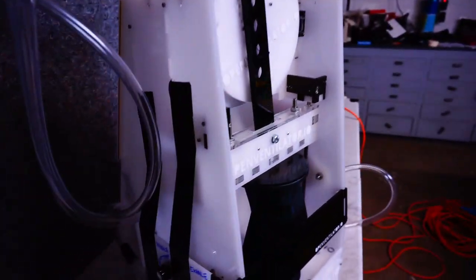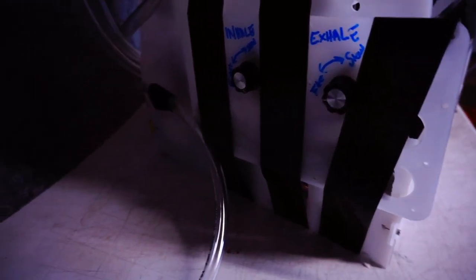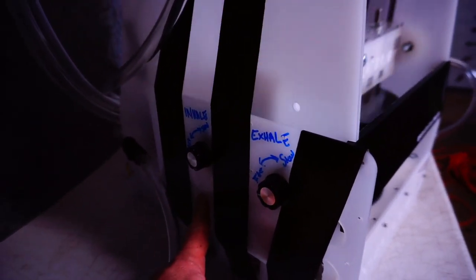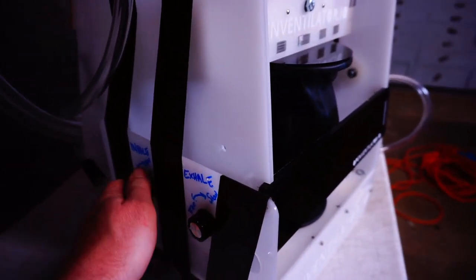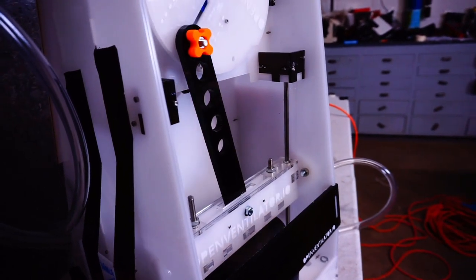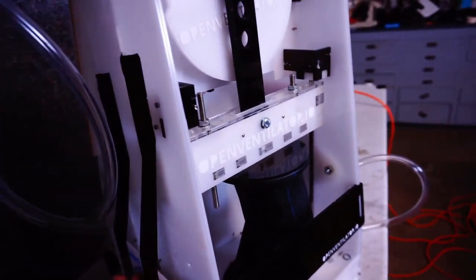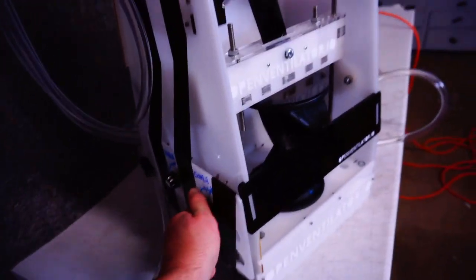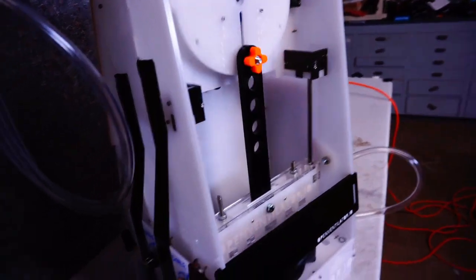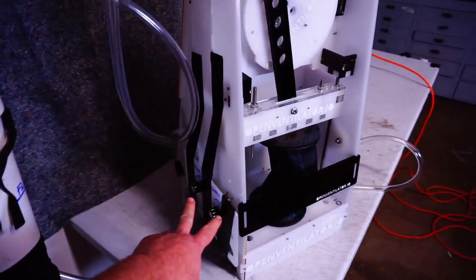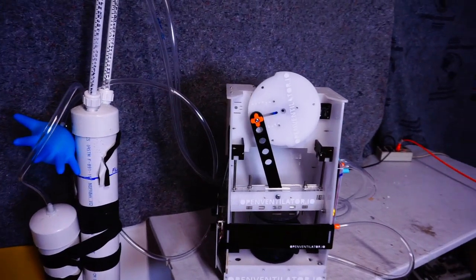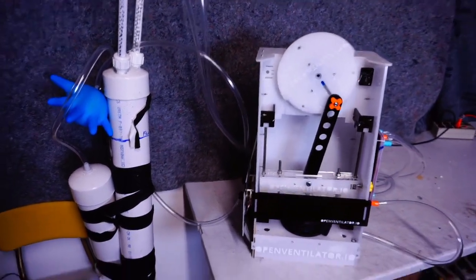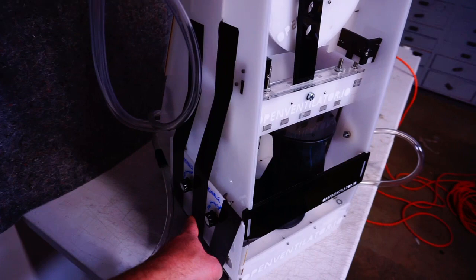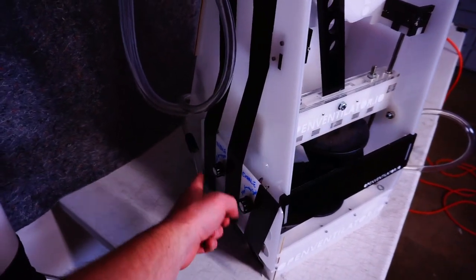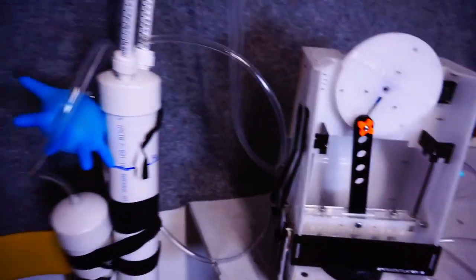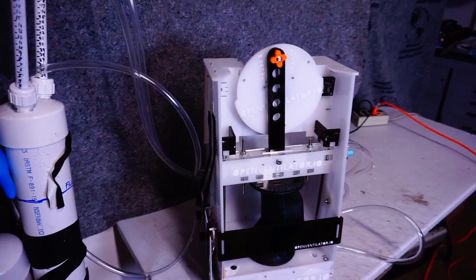Okay, so over here, pardon my electronics mounting, we have an exhale speed and an inhale speed. We're now, let's say, on the inhale cycle. We can slow that way down, or speed it way up, and the same for the exhale. By changing these two speeds, we can change the ratio of inspiratory versus expiratory timing, and also the total breaths per minute. On this machine, we don't indicate an actual speed or BPM per click on each one of these dials, because the resistance of the lung will also change the motor speed.